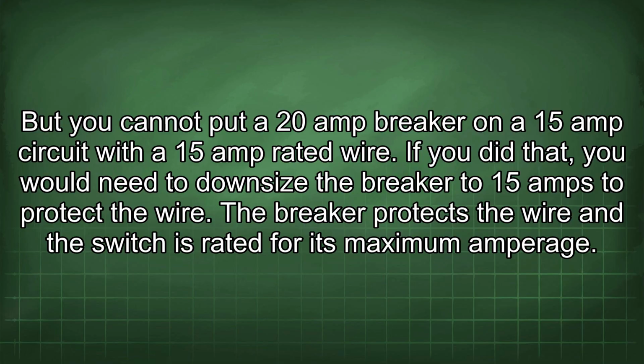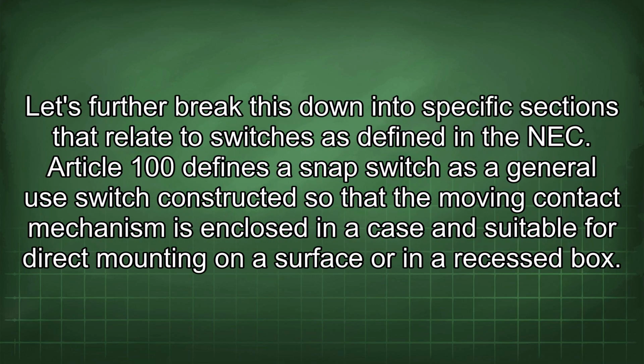If you did that, you would need to downsize the breaker to 15 amps to protect the wire. The breaker protects the wire and the switch is rated for its maximum amperage. Let's further break this down into specific sections that relate to switches as defined in the NEC.